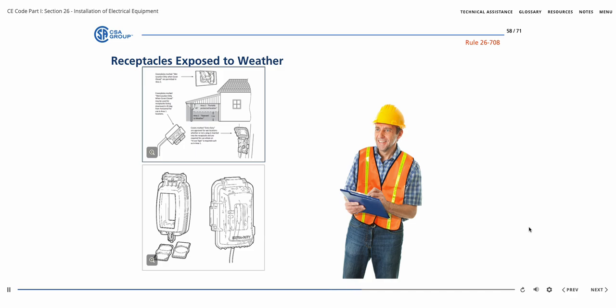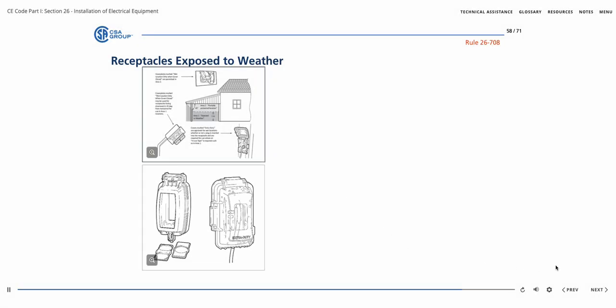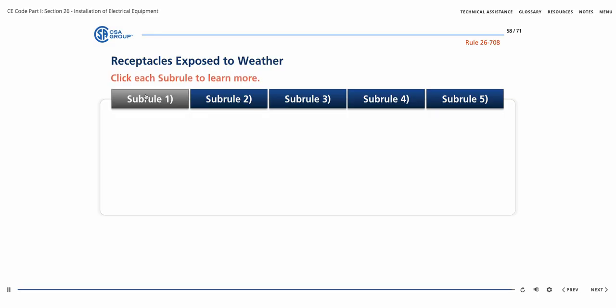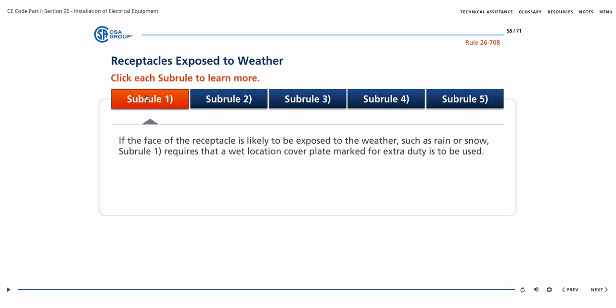When used in this fashion, there is a risk that long-term exposure to moisture can cause the receptacle to corrode, and if the receptacle is equipped with GFCI protection, that protection might malfunction, creating a fire and shock hazard. In some cases, these receptacles can be installed where they are protected from the weather, such as under an eave or an overhang. If the face of the receptacle is likely to be exposed to the weather, such as rain or snow, Subrule 1 requires that the wet location cover plate marked for extra duty is to be used.